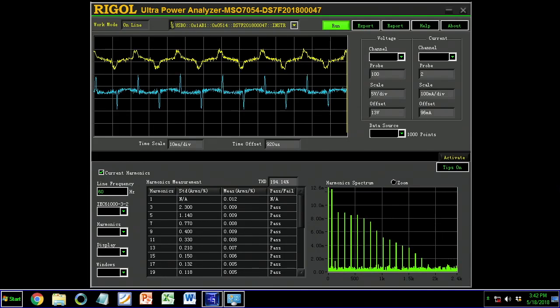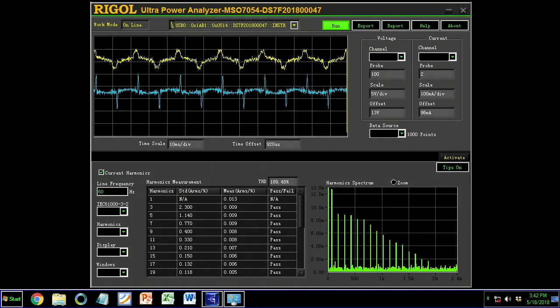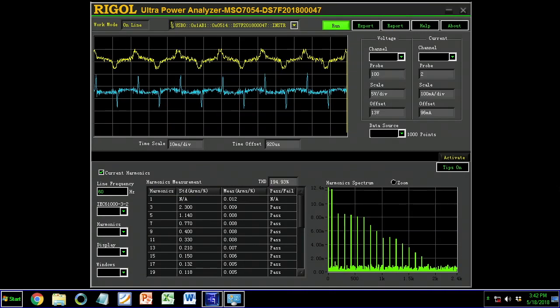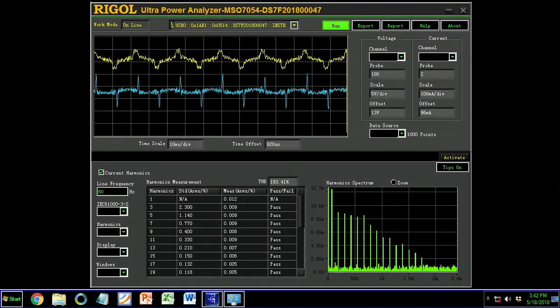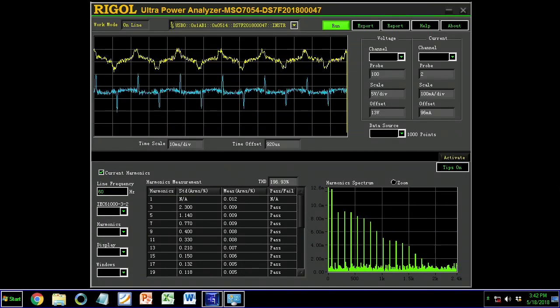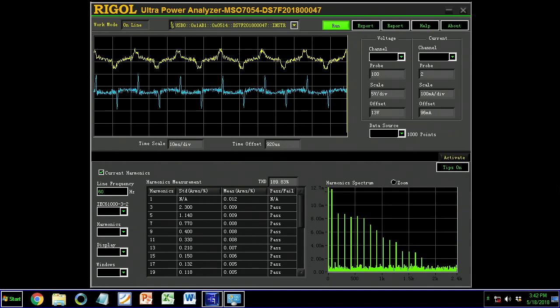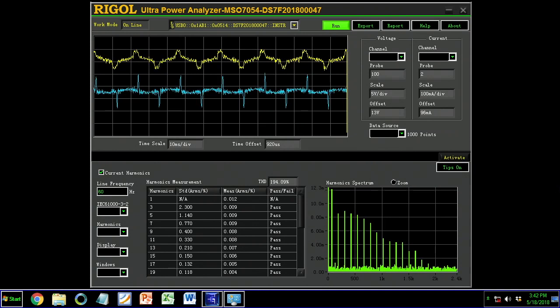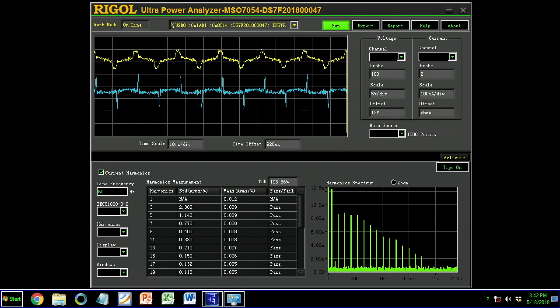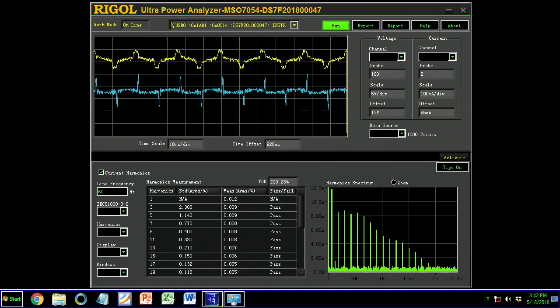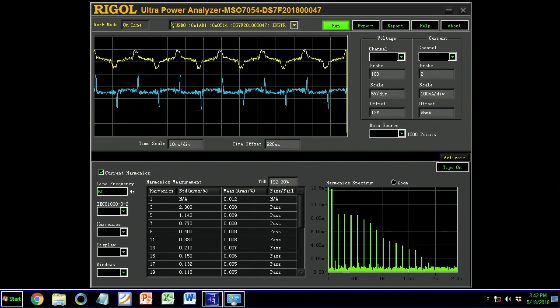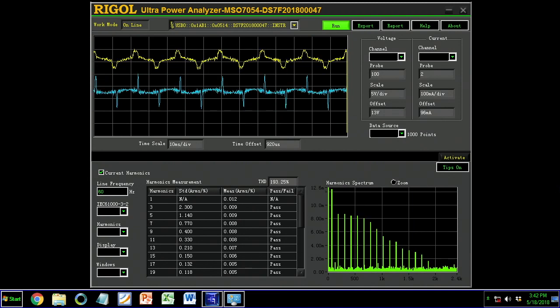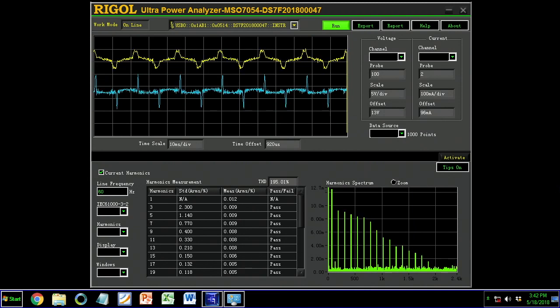Here, the software is calculating the current harmonics within your signal by using both the voltage and current measurements together. You can also do things like safe operating area and other measurements within the Ultra Power Analyzer software to give you a complete look at all your power analysis needs.